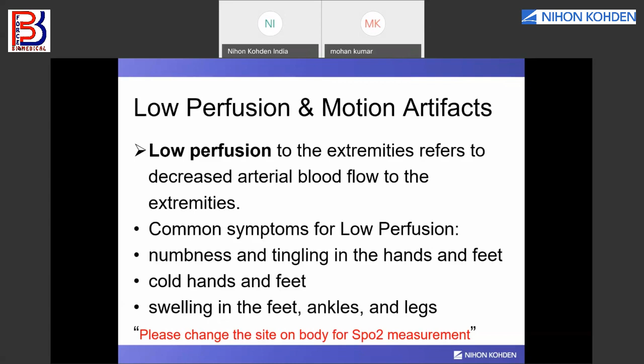Other causes for incorrect reading in pulse oximetry are hypoperfusion that we see in low perfusion, vasoconstriction, calloused skin, or excessive movement, what we call motion artifact, or incorrect sensor application. There could be other critical patient conditions. Now, we cannot change the patient. So what do we do? We change the setting inside the parameter monitor to get proper SpO2 reading.